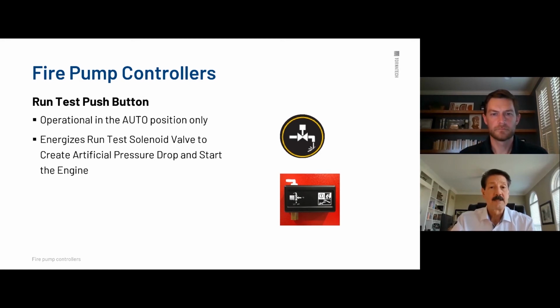Again, we talk about the run test push button. As I mentioned, similar to the electric itself, what we have is meeting NFPA 25 requirements as you do weekly tests of the engine itself for 30 minutes. Runs a cycle. You can press this button. It drains minimal water out of that test solenoid right here. And basically what's going to happen is it'll just use a little bit of water. It'll exercise the pressure transducer, drop in pressure. It'll run for 30 minutes and then shuts off, but it records it as a test.